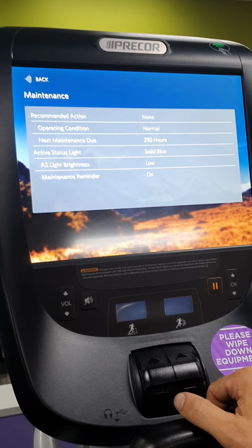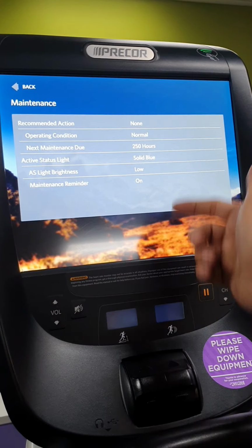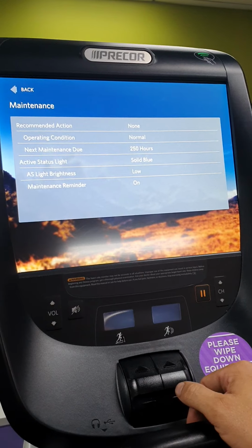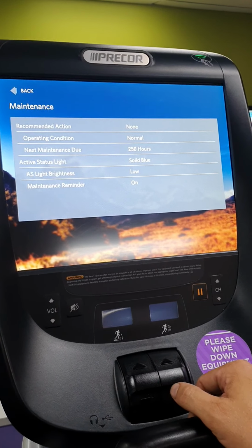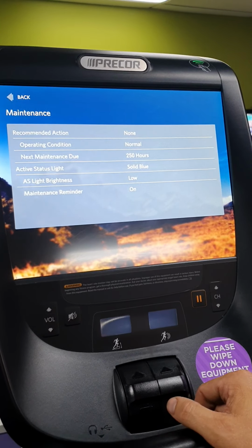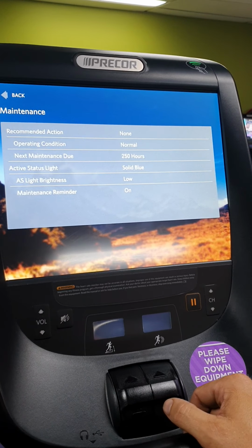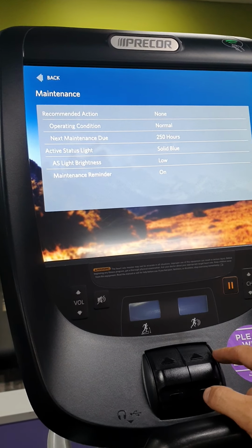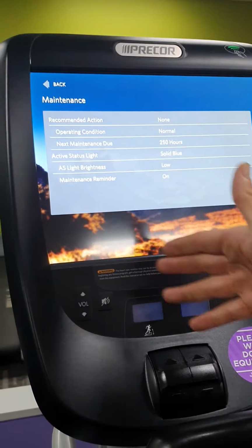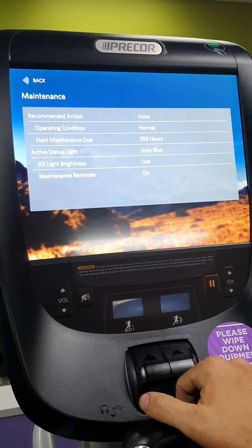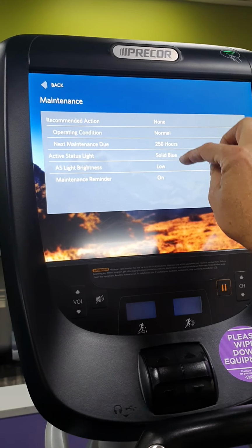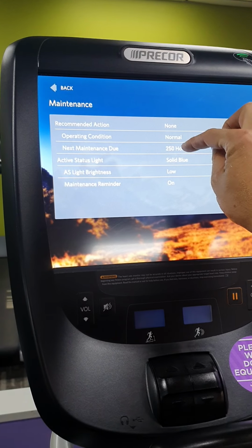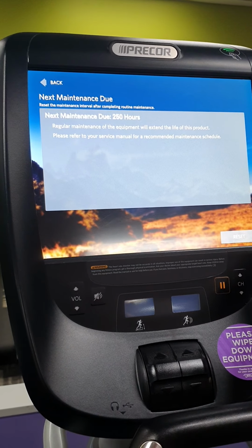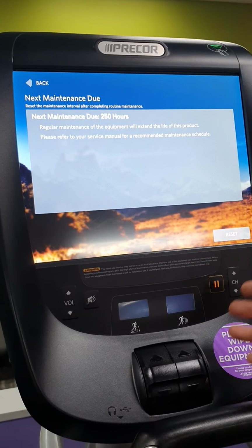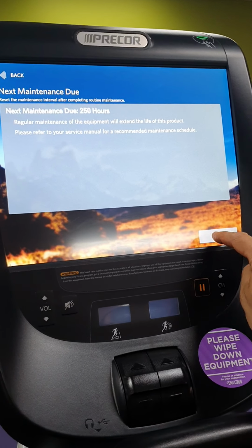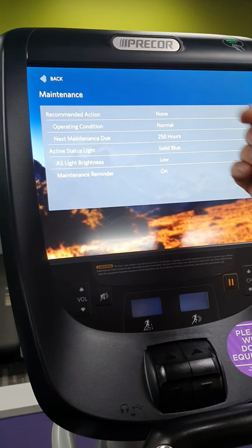That means there's 47 hours left of the 250 hours before it's due for a maintenance, which means just a quick look over, maybe a vacuum inside the back covers and check there's no clunking or grinding noises on the machine, and also prompts to do a screen calibration on the console, which I'll show you in a minute as well.